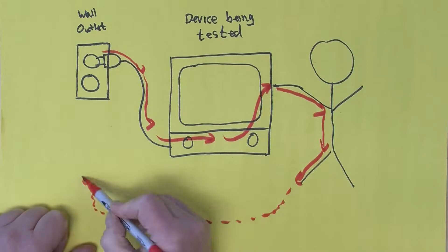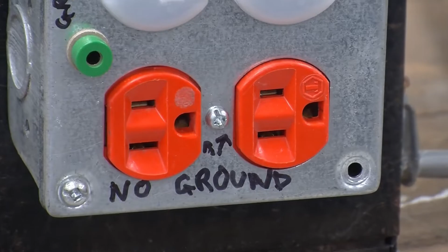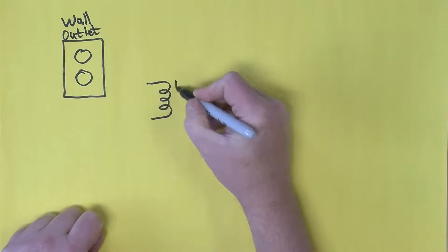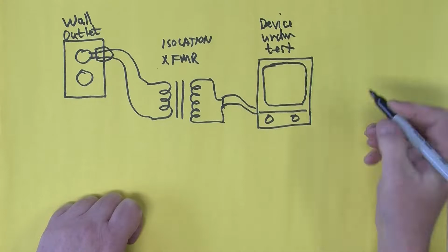By having an isolation transformer where the primary and secondary coils are not connected in any way, you make that return connection much harder. If I were to touch either of the powered terminals of this plug on the isolation transformer, in theory there should be no way for current to go down my arm and through my body into the ground, because there's no electrical connection between the secondary coil and the primary coil.